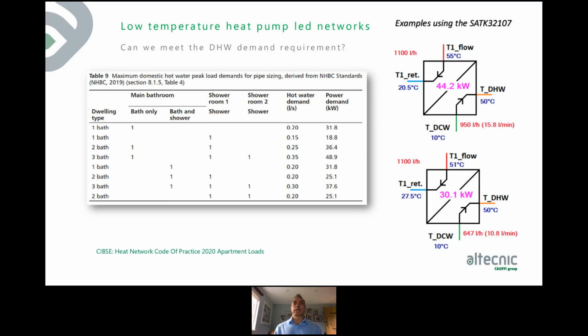So the first one, the table on the left is just straight from CIBSE CP1. And what you can see on the right-hand side of that table is typical power demands, domestic hot water demands for typical apartments shown on the left at different types. Now you can see the top right calculation from our SATK 32107. If you have a 55 degrees C primary flow going in, you've got 44 kilowatts of hot water instantaneously from the unit. Now that covers pretty much the majority of these, all except the 3-bathroom apartments where we're pretty close.